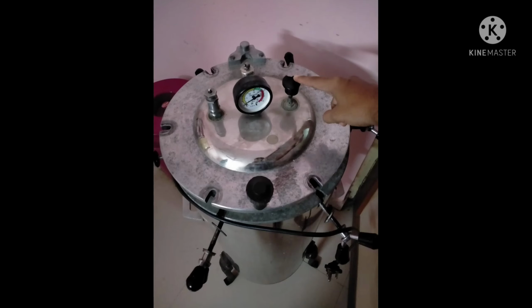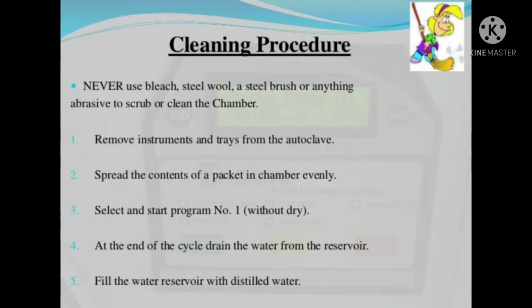So in short, it takes about 10 to 15 minutes to get the steam ready and the pressure built up, and after that 15 psi pressure and a temperature of 121 degrees for 30 minutes is sufficient for all ophthalmological instruments and materials. So a total cycle of 45 minutes is required for the autoclave. When the 45 minutes are completed, we switch off the autoclave and allow the steam to release slowly. This cooling also takes another 10 to 15 minutes. So the total cycle of autoclaving comes to around 1 hour. This is all about autoclaving.